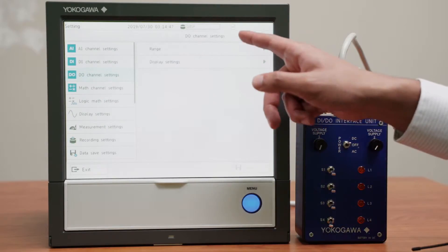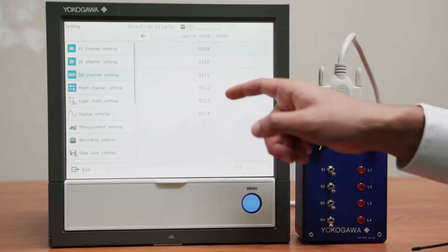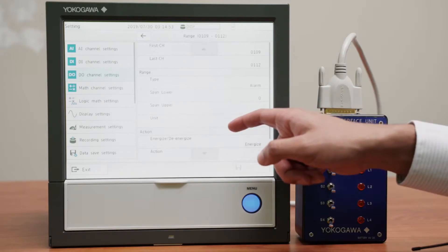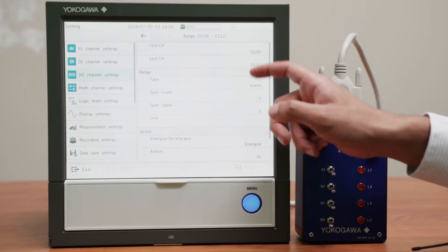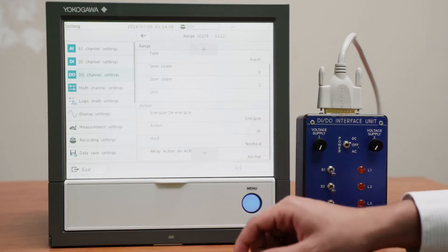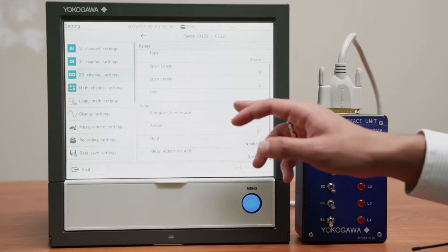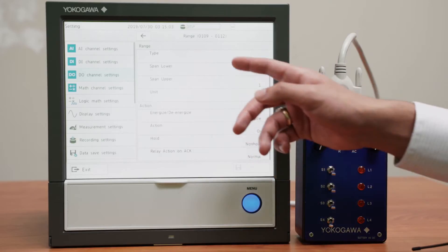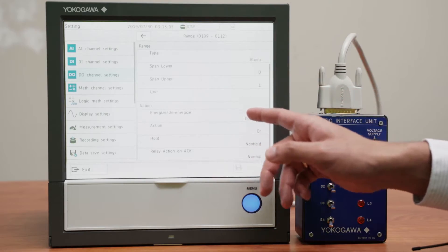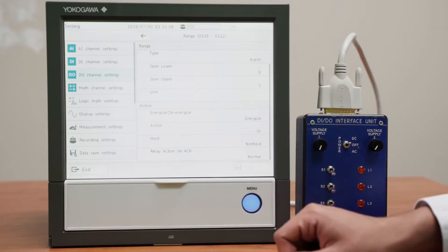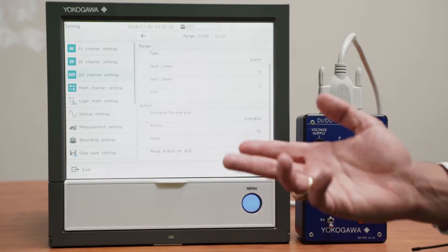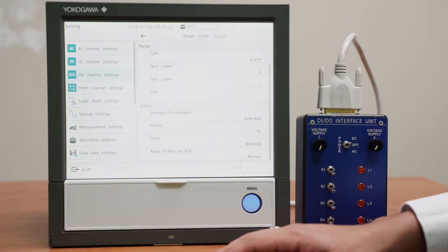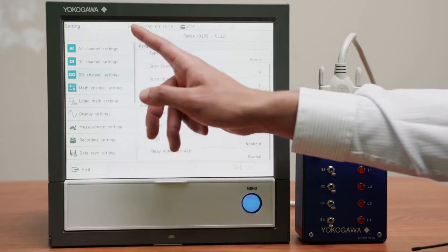Digital output. I'll go ahead and check also that they have the correct settings which they seem to have, 0 to 1, no unit. And if you want these to turn on when the alarm is set off, the type should be alarm. Then you will have them energize. If it were the other way around that you want the default to be on, you'd have de-energize, but that is not the case.